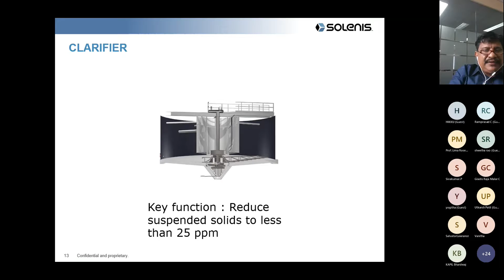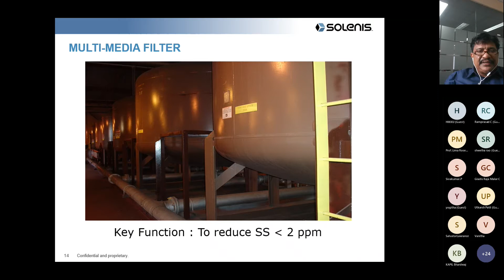So we have a combination of the coagulant and a flocculant, and by using this combination, we ensure that the particulate matter is coagulated and then flocculated and settles down. The parameter which we have at the outlet of the clarifier is less than 25 ppm. And then obviously this 25 ppm is not good enough to go downstream. So you need to pass it through a multimedia filter, which is a combination of anthracite, sand and pebbles. And then we bring the suspended solids down to less than 2 ppm.